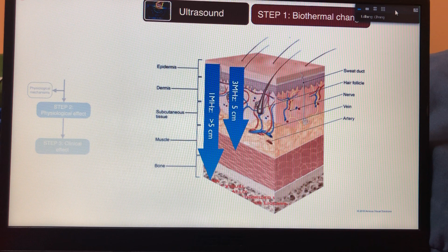This is a similar one for 3 megahertz. They're on the same scale. So you can see 3 megahertz really overheating the skin. And then when you go down to 5 cm, there's almost no energy left there. Whereas compared to 1 megahertz, the skin is not overly overheated, and at 5 cm you still have energy there. So this is your biophysical change. For biophysical change, 3 megahertz reaches 5 cm, 1 megahertz greater than 5 cm. It can actually go more than that. We haven't measured past 5 cm, but it can go much more than that.